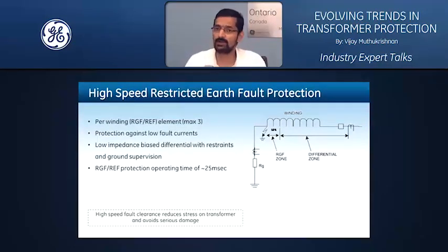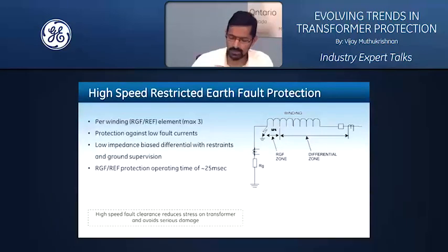And the operating speed of restricted ground fault protection can also make a big difference. A 25 millisecond operating time in the case of the 845 really is high speed for a restricted earth fault protection operation. Again, the value here is that you are isolating the fault, reducing the stress on the transformer, and preventing serious damage to the transformer. This is on the dependability aspect of the differential protection.